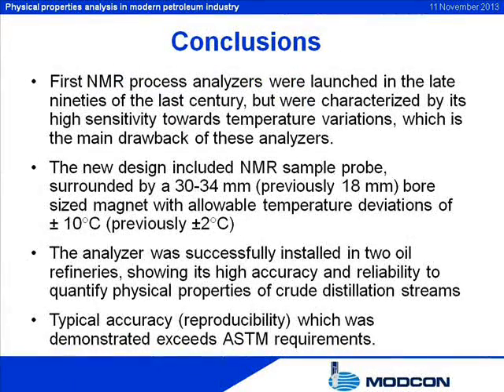The first NMR process analyzers were characterized by high sensitivity towards temperature variations, especially in cases where process streams of different temperatures and viscosities must be measured. To achieve maximum homogeneity and stability of the magnet, temperature fluctuations must be insulated to prevent influence on the magnet properties. Therefore, the primary task was eliminating high susceptibility to temperature deviations between process streams. The new design included a total innovation in hardware and software, with the analyzer containing a sample probe surrounded by a 30-to-34-millimeter (previously 18-millimeter) bore-sized magnet.